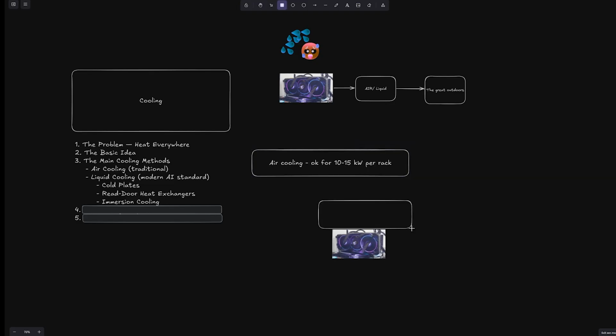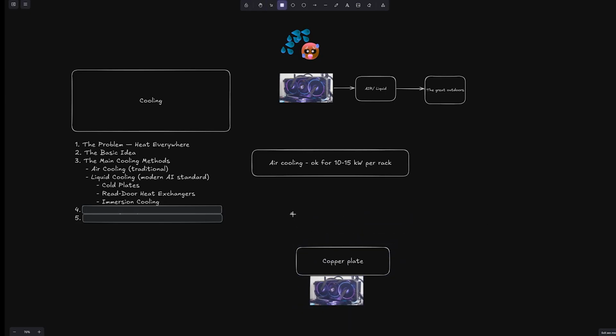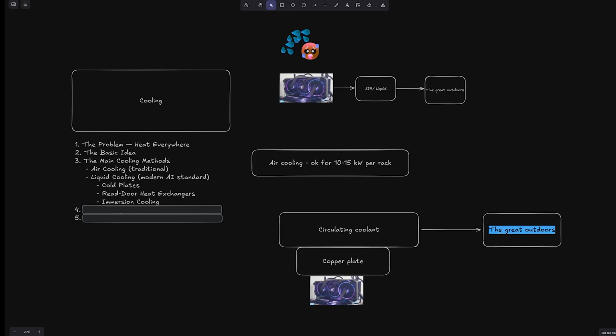The modern AI standard is liquid cooling though. It moves heat with water or dielectric fluids directly from components. There are a few ways that liquid cooling works: through cold plates, where water channels sit directly on GPUs or CPUs, and the heat flows from the chips to the copper plate to the circulating coolant. The warm coolant leaves the rack, passes through a heat exchanger, and dumps heat outside via chillers or dry coolers.